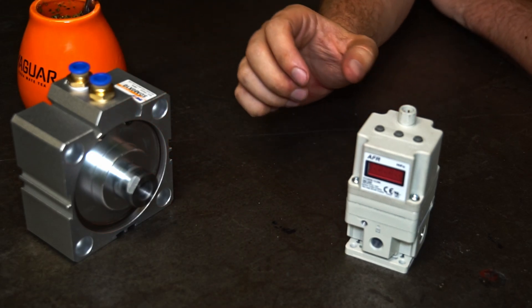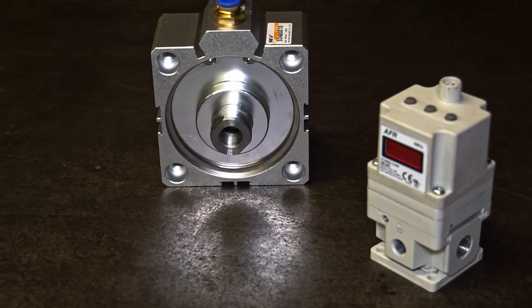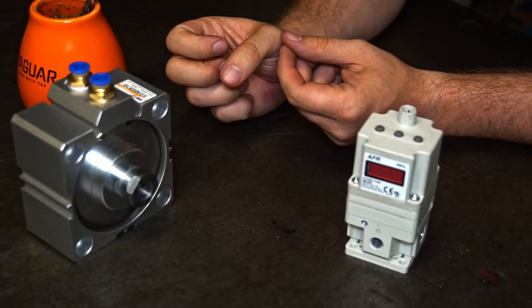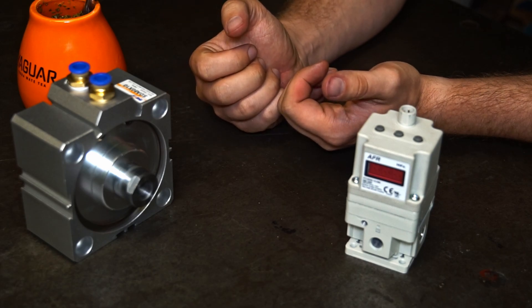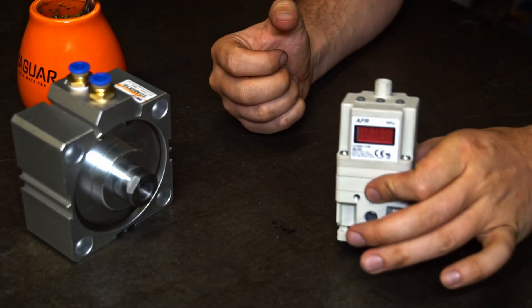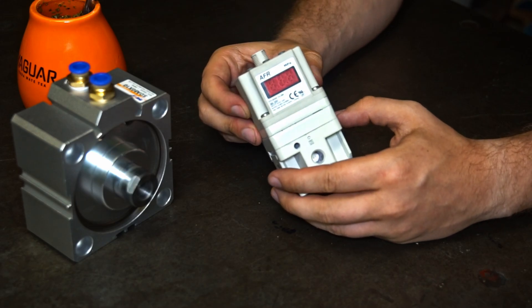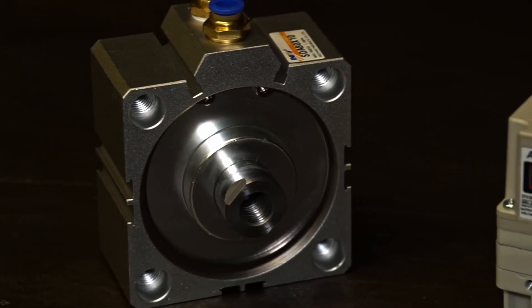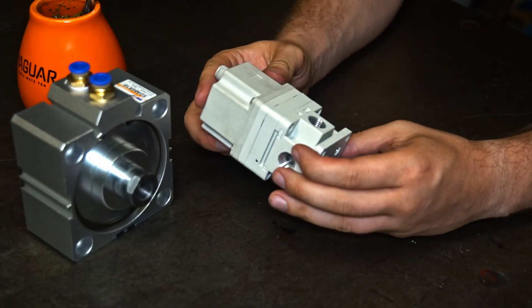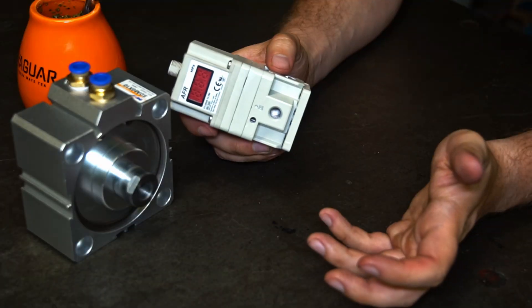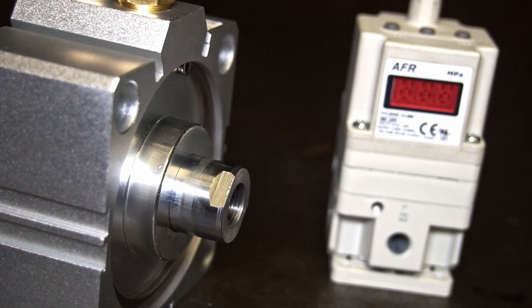To sum everything up, the device seems to be fine for forcing air cylinders to do something else they usually do in their size using electricity. It will work in other applications as well. It regulates quite responsive and precise the air pressure on its output. The pressure range is between 0 and maximum supplied to the air input. I bought mine for max 10 bar, quarter inch sockets, voltage input signals and 0 to 5 volt monitor output.